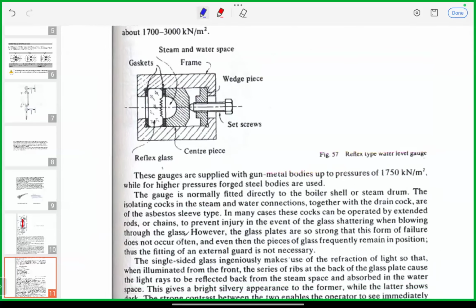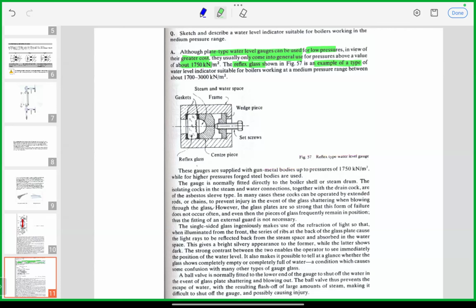Plate type water level gauges can be used for low pressure. In view of their greater cost, they usually only come into general use for pressures above 17 bar. The reflex glass is an example of a water level indicator suitable for boilers of medium working pressure. These gauges are supplied with gunmetal bodies.